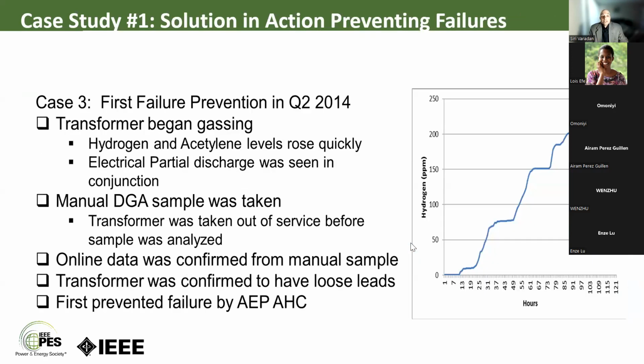There was another example where the transformer started gassing very unusually. Hydrogen and acetylene levels rose very quickly. Partial discharge was seen in conjunction, and the transformer was again taken out of service.